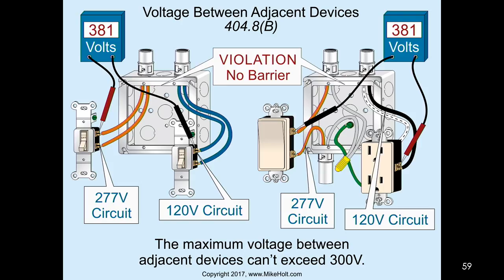Now, the rule said between adjacent devices. So it could be a switch and a receptacle. The same thing applies here. The voltage between adjacent devices shall not exceed 300 volts. You're fine unless you get into 480 volt systems. But I could have a 2-pole switch with a 480 volt circuit coming to it, and it's not a problem that 480 is on a single device. I just can't have it on adjacent devices. You can't have two switches. One switch at 480 is fine because it's a single switch. You just can't have it on two.